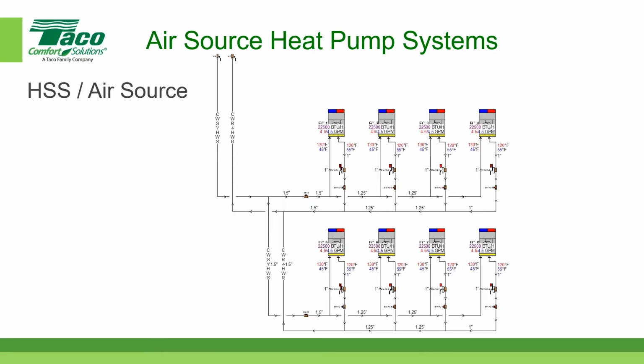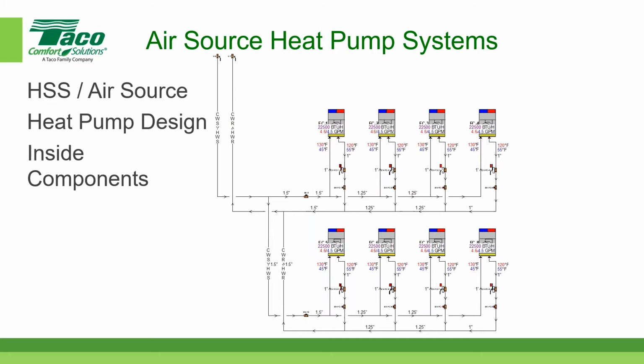Okay, so now here are the heat pump design inside components. There are those 2 valves again. There's my supply water temperature, going to my fan coil. In this case, it's a very simplified fan coil system. I've got 2 floors with 4 fan coils on each floor. And I'm using a conventional piping system to accommodate that.